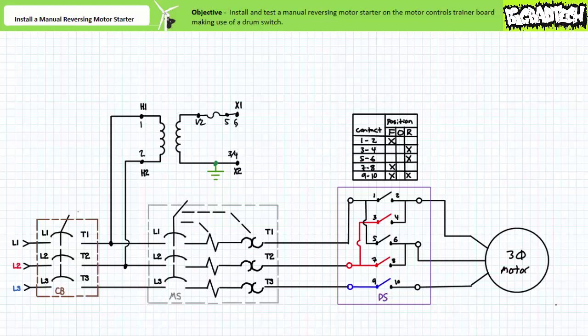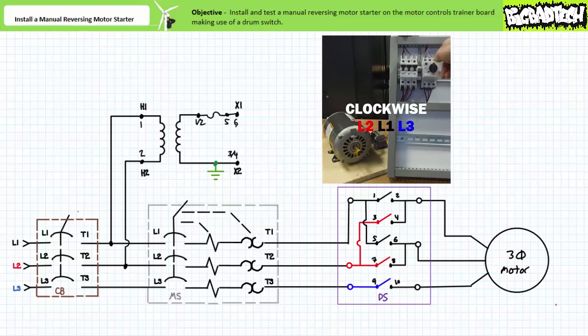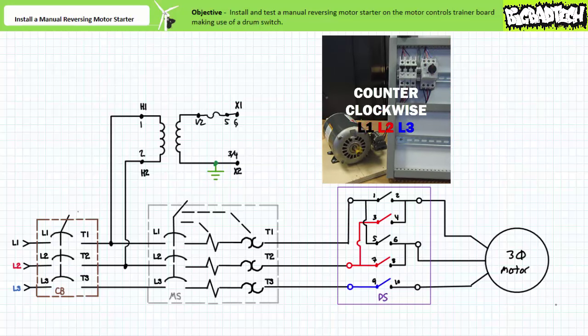To change direction of rotation, a technician must lock out and tag out the system, swap any two hardwired phase connections, and return it to service. This particular hardwired manual motor starter rotates the motor clockwise. This particular hardwired manual motor starter rotates the motor counter clockwise.